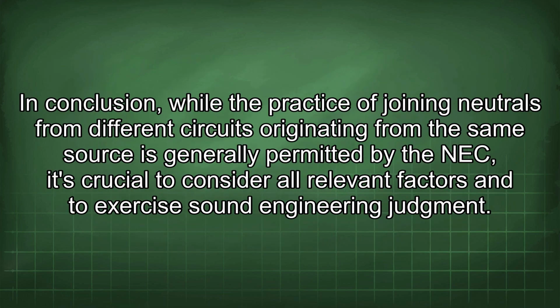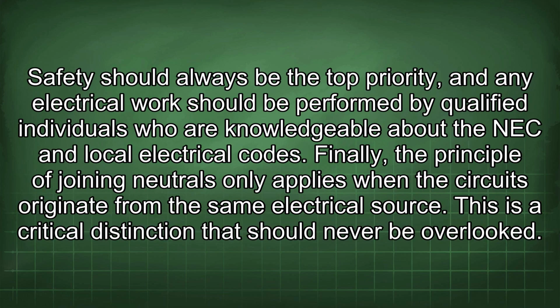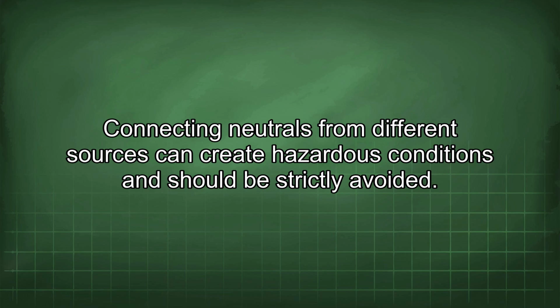In conclusion, while the practice of joining neutrals from different circuits originating from the same source is generally permitted by the NEC, it's crucial to consider all relevant factors and to exercise sound engineering judgment. Safety should always be the top priority, and any electrical work should be performed by qualified individuals who are knowledgeable about the NEC and local electrical codes. Finally, the principle of joining neutrals only applies when the circuits originate from the same electrical source. This is a critical distinction that should never be overlooked. Connecting neutrals from different sources can create hazardous conditions and should be strictly avoided.